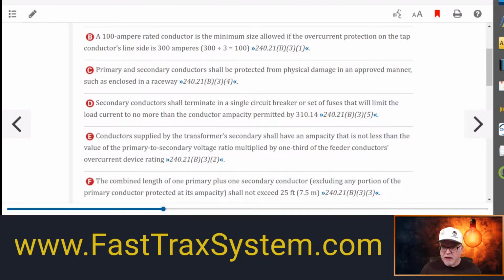Let's see here, 240.21. All right, so you may run into this scenario. You may be asked to run a feeder, and you're running it out to other loads, and they size it adequately, and they did the load calculations, but now they're saying, hey, I need you to tap off of that feeder. It's adequately sized, you hope that's been done, and now it's going to feed a transformer. What are the rules? Okay, well, let's go down, and what we're going to look at is here, okay?